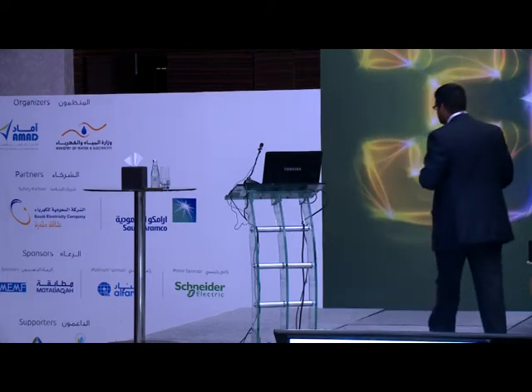What we strongly recommend is to actually go out and do it immediately. Supply your entire workforce with arc risk category 2 type of clothing. Once again, I don't sell clothing, so I'm not trying to do any marketing here. Because what's very important is that arc rated clothing will not burn. Arc rated clothing will not burn.